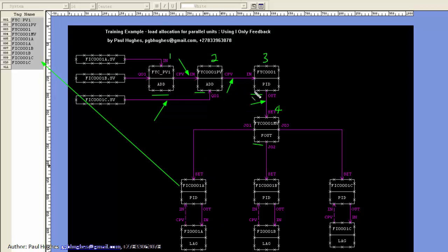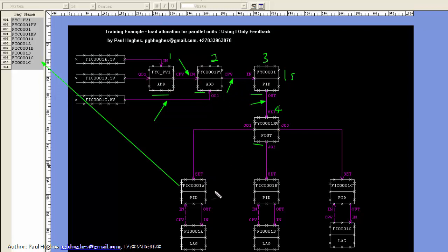The integral time of one second was working with no problem largely because the sequence of blocks is in the correct order of execution — the feedback is calculated first, then the PID, then the output. This correct sequencing is critical for stable integral-only control.